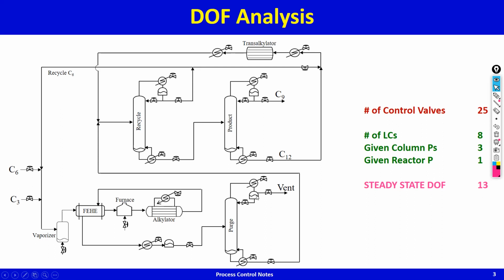What's the other one going to be? You want to condense everything that can be condensed, because you don't want benzene to leak out the top. So maximum condensation will happen if the condenser temperature is as low as possible, and if you're using cooling water in the condenser, let's say cooling water is available at 30 degrees Celsius, so a condenser temperature of 45-50 degrees Celsius is about as low as you can get, and that ensures as little benzene as possible leaks out in this C3 vent.